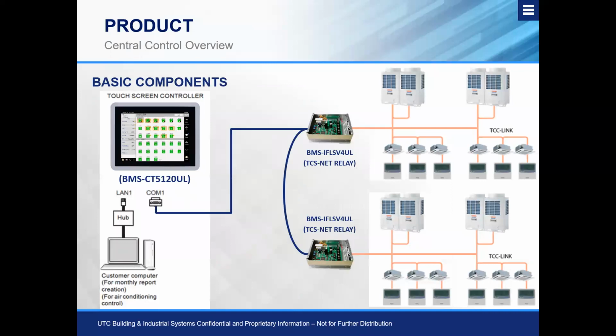We have our centralized control, where each one of these TCS net relay interfaces converts this Toshiba Carrier protocol over into how we can interpret it on the touchscreen controller. Each can handle 64 indoor units. If we have multiple systems and more than 64 indoor units, all we do is add a second net relay interface, which can feed on a common control line back to the centralized control. So it's important to know that if we have over 64 indoor units total between multiple systems, we need two of these net relay interfaces.